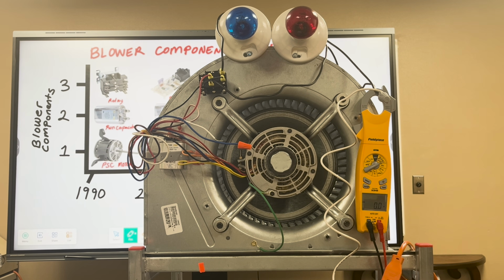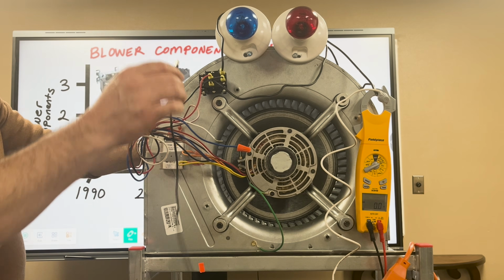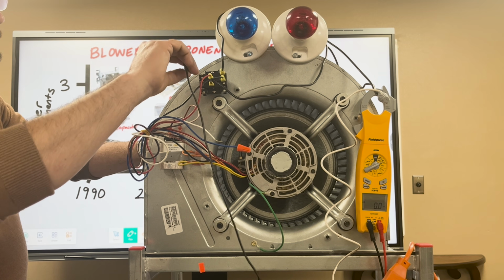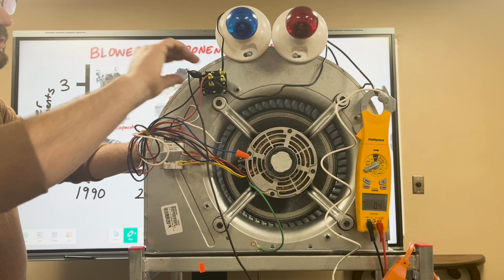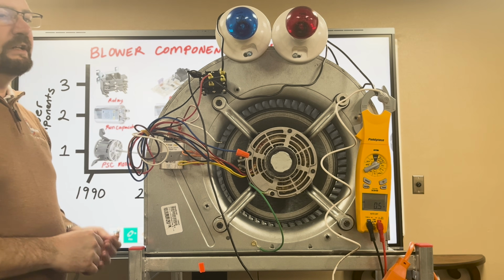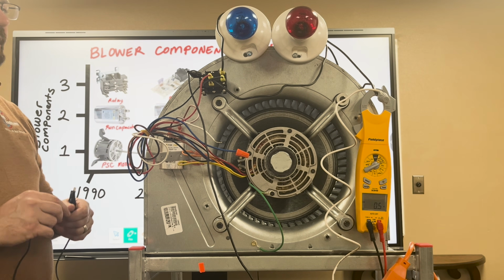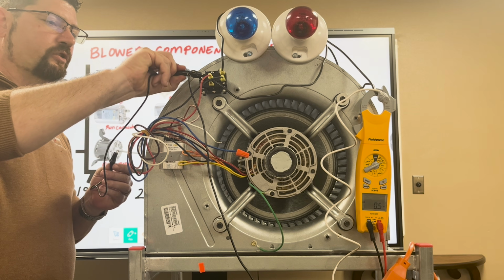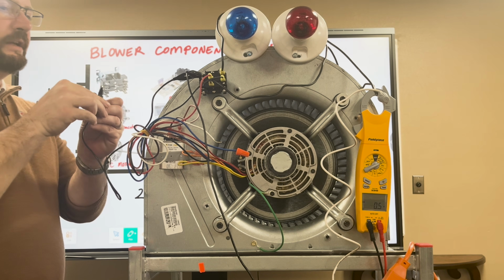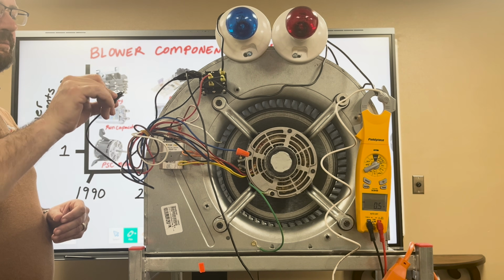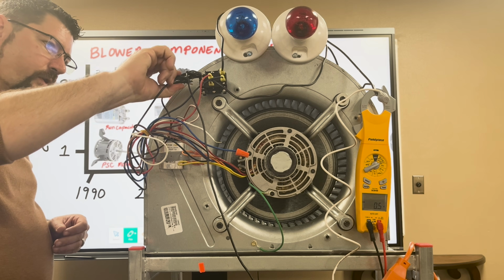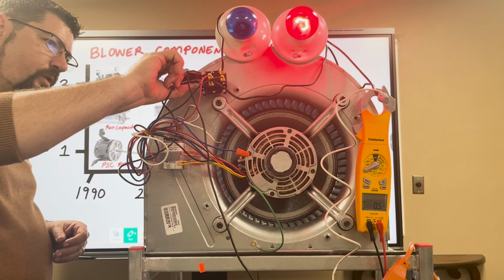So I'm going to come around on the other side. We're going to take our line voltage and put it up on terminal 1. Because I have 2 poles that need that same leg, I'm going to come off of terminal 1 and energize terminal number 4, which would be the second pole.